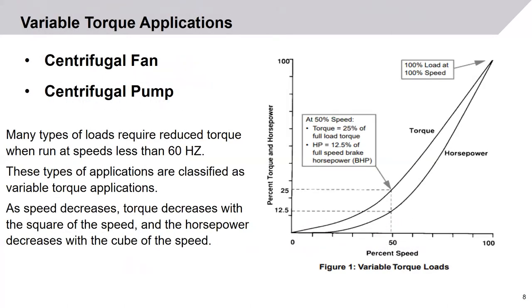There are two types of applications to consider. Variable torque applications include centrifugal fans and centrifugal pumps. In these types of loads, they require less torque at speeds less than 60 hertz. There are significant energy savings available by running below 60 hertz. As speed decreases in these applications, torque decreases with the square of the speed and motor horsepower decreases with the cube of the speed.